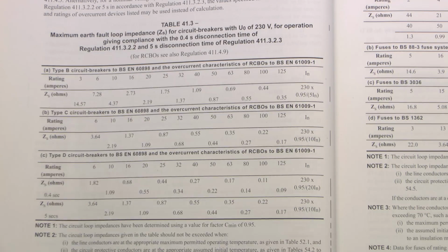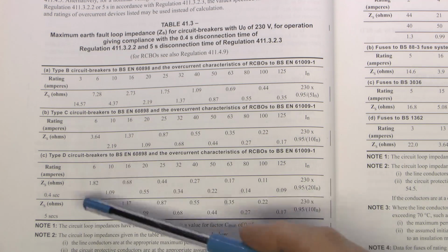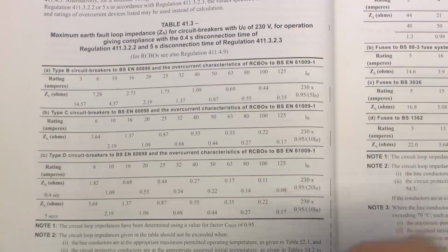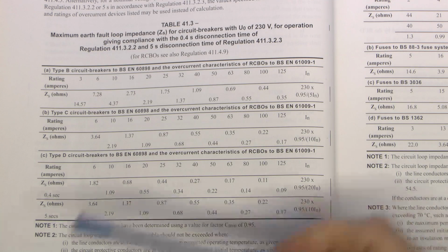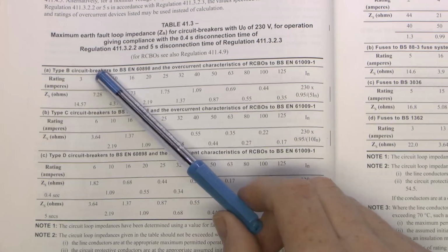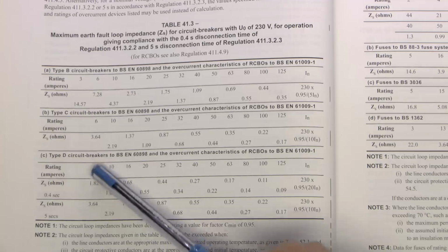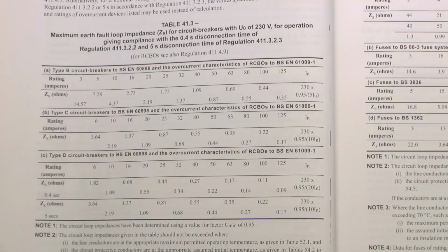And in very extreme cases, you may find it doesn't actually trip at all. All that would happen is that the cables would just get rather hot and melt, possibly set on fire. The circuit breaker would just sit there doing very little. So it is important to check these things before just shoving in the circuit breaker. Now, of course, on a 6 amp circuit, it's fairly unlikely you're going to have impedances anywhere near these things, unless it's, say, ridiculously long or something.